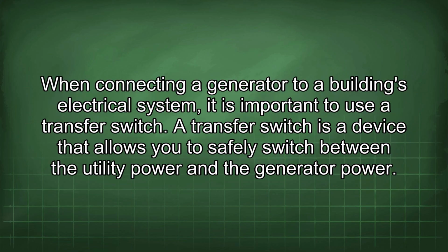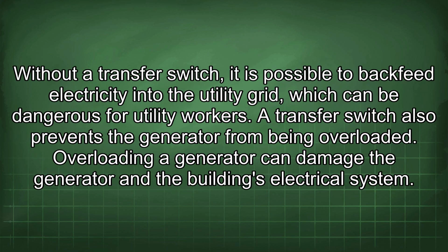When connecting a generator to a building's electrical system, it is important to use a transfer switch. A transfer switch is a device that allows you to safely switch between the utility power and the generator power. Without a transfer switch, it is possible to backfeed electricity into the utility grid, which can be dangerous for utility workers. A transfer switch also prevents the generator from being overloaded. Overloading a generator can damage the generator and the building's electrical system.